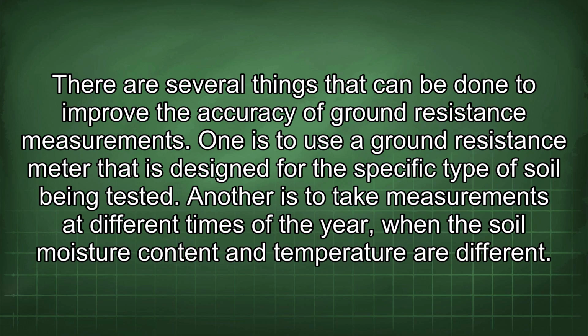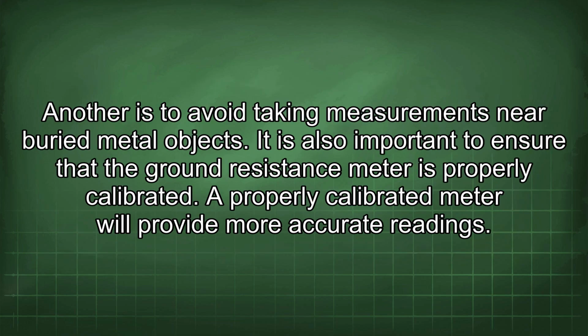One is to use a ground resistance meter that is designed for the specific type of soil being tested. Another is to take measurements at different times of the year, when the soil moisture content and temperature are different. Another is to avoid taking measurements near buried metal objects. It is also important to ensure that the ground resistance meter is properly calibrated. A properly calibrated meter will provide more accurate readings.